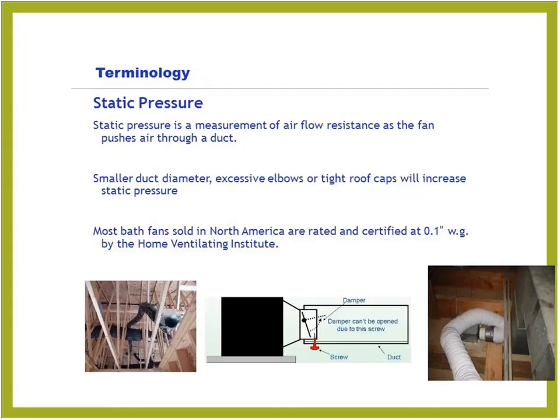So here are some pictures of some common install mistakes. I'm sure most of you have probably seen some of these, where the takeoff is pointed in the wrong direction, as we have in that far right picture there. Look at the amount. If every 90-degree turn adds an equivalent of 10, or in the case of flex duct maybe 15 feet of equivalent length in terms of static pressure, in that picture on the far right we've got 1, 2, 3 90-degree turns before we get a foot away from the fan. So certainly not an optimal install there.